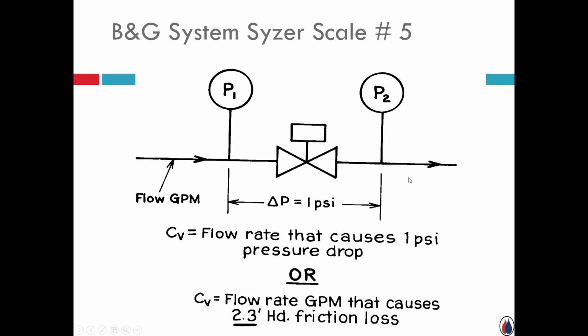Picture speaks 1,000 words. Here's a valve. I have an inlet pressure. I have an outlet pressure. Whatever flow rate is required to create that 1 pound pressure drop. Or when you look at scale 5 and you say, hey, 1 PSI on the scale 5 curve is lined up opposite the letters C sub V. Straight up, if you convert it and we're dealing with basic water, the equivalent would be 2.3 feet of head. You can have 1 pound pressure drop or 2.3 feet of head. So all of a sudden you can start using that valve to establish flow rates. You know the pressure drop.